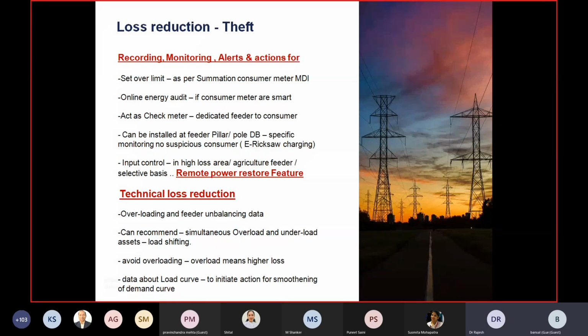We have added parameters where we can set limits. Suppose there's a 400 ampere ACB. Today a 400 ampere ACB normally trips between 70 to 90% of the set value. Here, even for a 400 ampere, I can set it at 100 amperes, because in winter my loads are low, so I can set it lower.